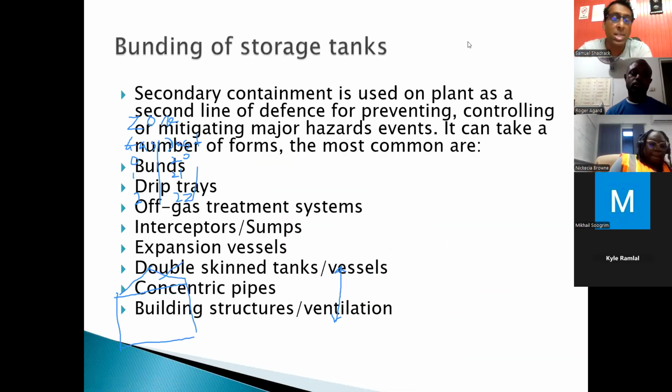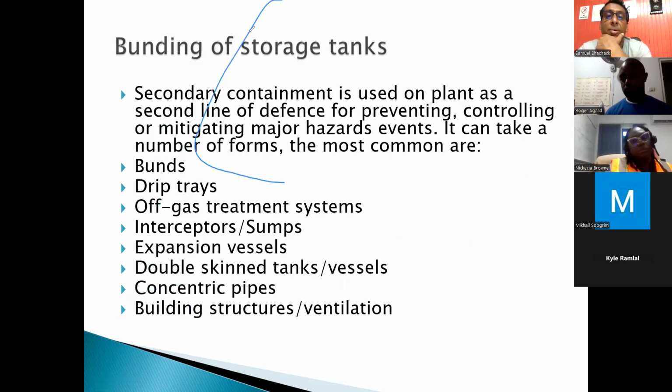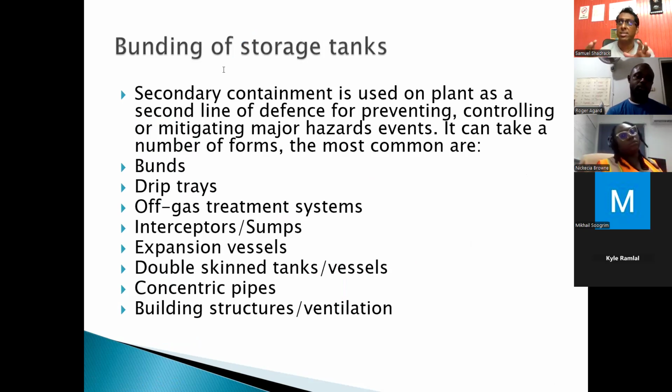We spoke about bunding. Let me just take a look at the time. We already discussed bunding and how bunding can be done via a series of collection pits. And your bunded area must be large enough. The only way to do that, like I said, is a series of pits. It must be large enough to withhold 110% of your tanks. If you work in the industry, you see how that is done?